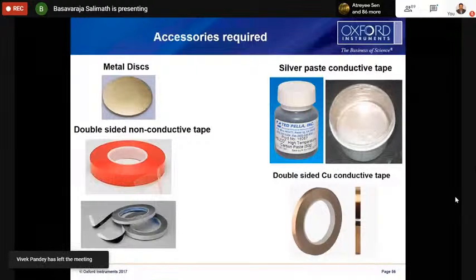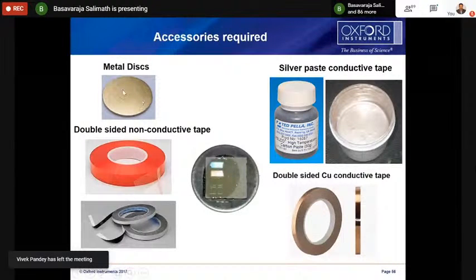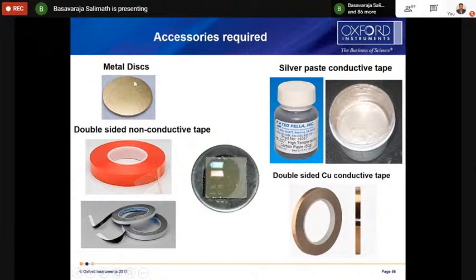And as for what accessories we can use, you can use a metal disc. This is a steel disc, or you can even use a glass slide or cover slip. On top of that, you need to put some double-sided tape. This is a black one, you can see that is a double-sided tape. On that, you put the sample. Now you can take this and use it for AFM imaging. If you are doing electrical measurements, as I mentioned, like conductivity property measurements, then instead of using this non-conducting tape, you can use conducting tapes like copper tape or silver paste.